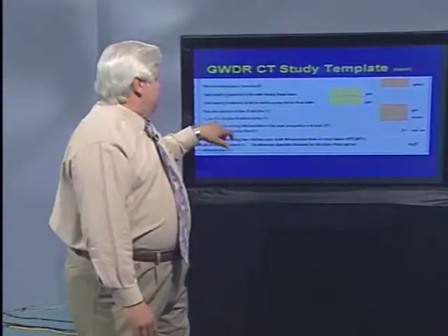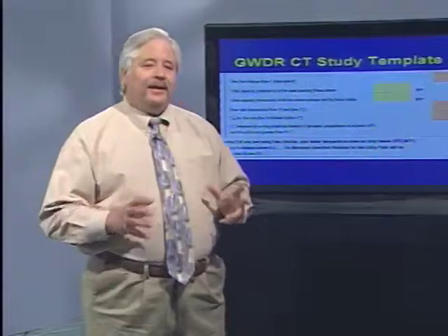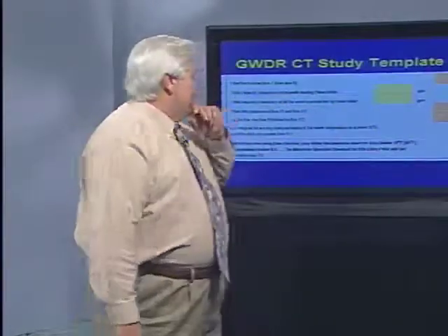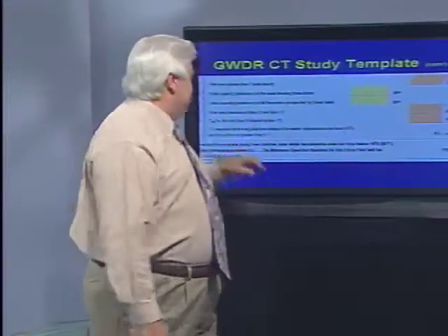Okay? The T10 for this site is just taking the effective gallons divided by the flow rate, and it calculates the T10 detention time within that plant. Why do we use T10? That's a really good question. Joaquin asked me that question.